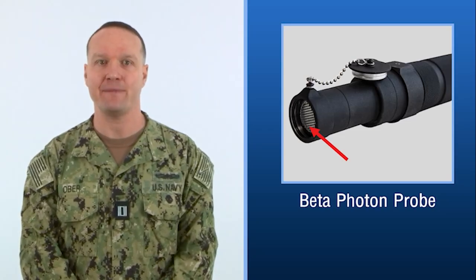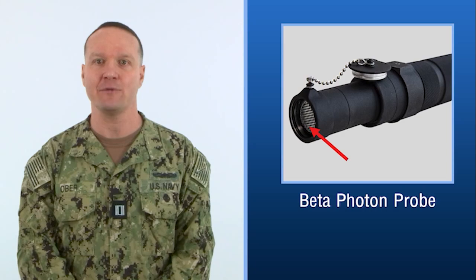As is in the name, the beta photon probe detects both beta and photon radiation. The end of the probe with a cap has a low-dose Geiger-Müller tube sealed by a mica window thin enough to allow beta and gamma radiation to pass into the tube. Inside the tube is a positive electrode or central wire and a negative electrode on the sides. Radiation enters the tube and ionizes the gas inside, which creates positive and negative charged particles. The negative charged particles migrate towards the positive charged electrode, and the positive charged particles go to the negative electrode. This change in charged particles directly correlates to the radiation measurement.